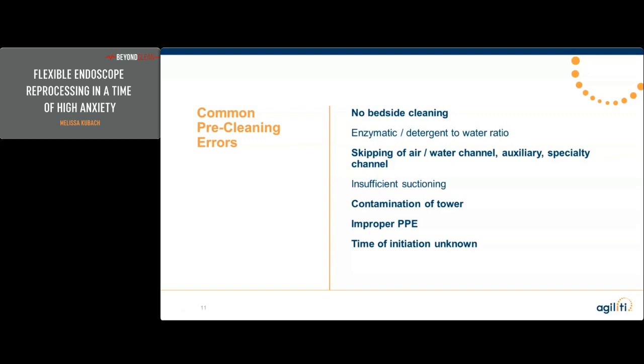I find about 30% compliance across the United States. A lot of people tell me, this is just going to be cleaned anyway, so why do I have to do this? What they fail to realize is that this is the first reduction in bioburden, the first reduction of logs associated with that bioburden. If this isn't done correctly or in a timely manner, the subsequent technician who has to clean this scope may not be able to get anything in or out of those channels. It may become humanly impossible to remove at some point, and for patient safety, this is one of the most important steps.